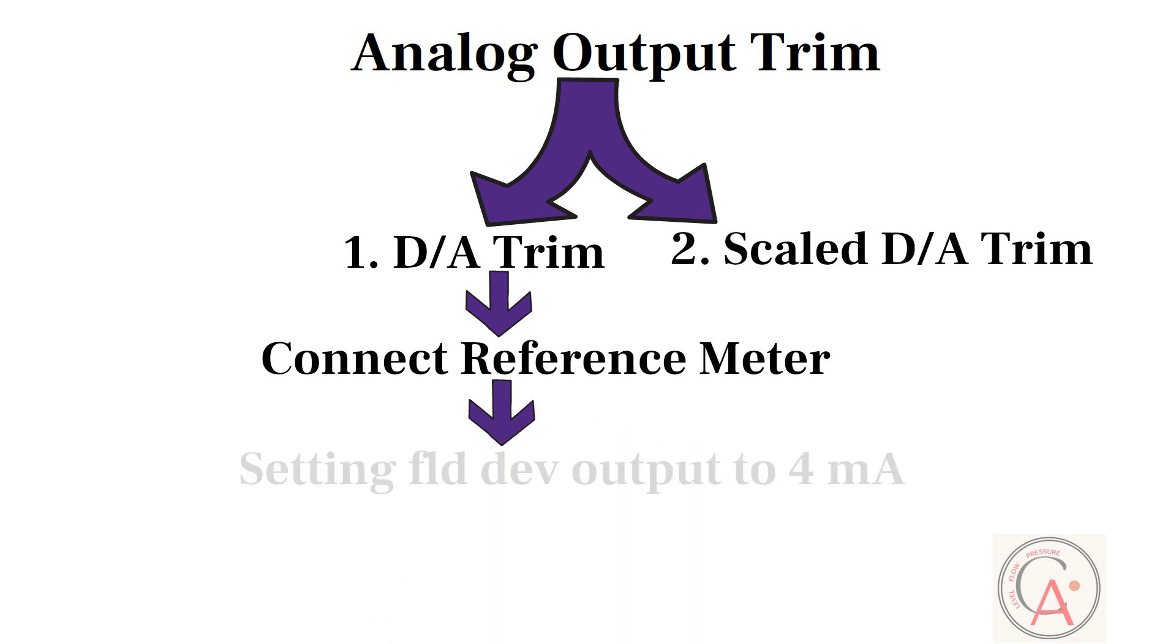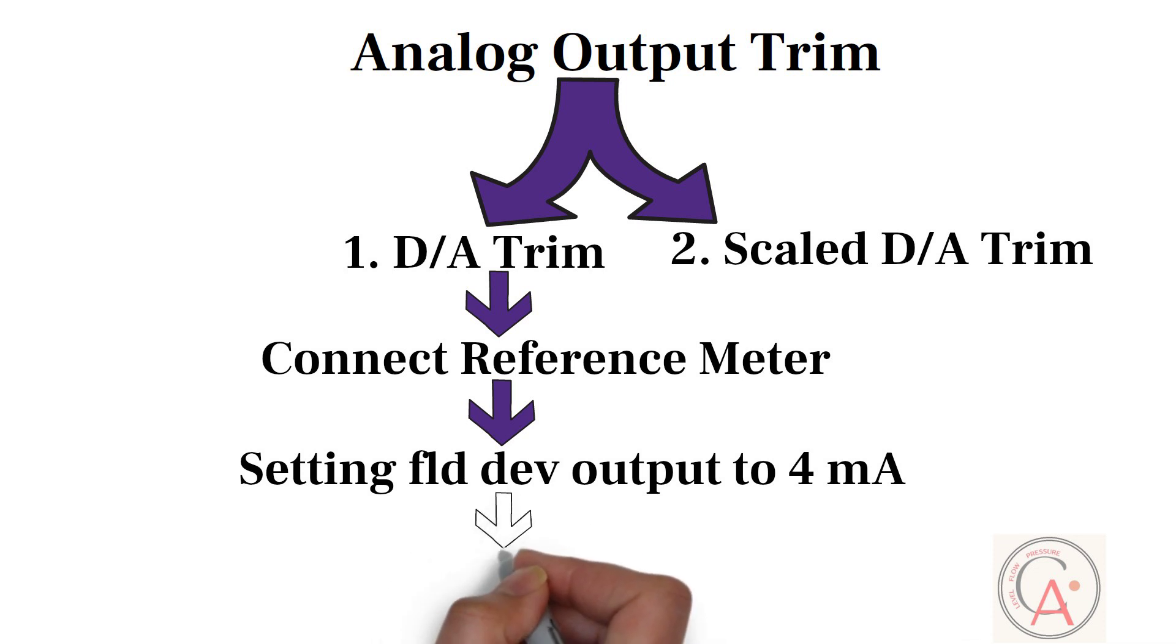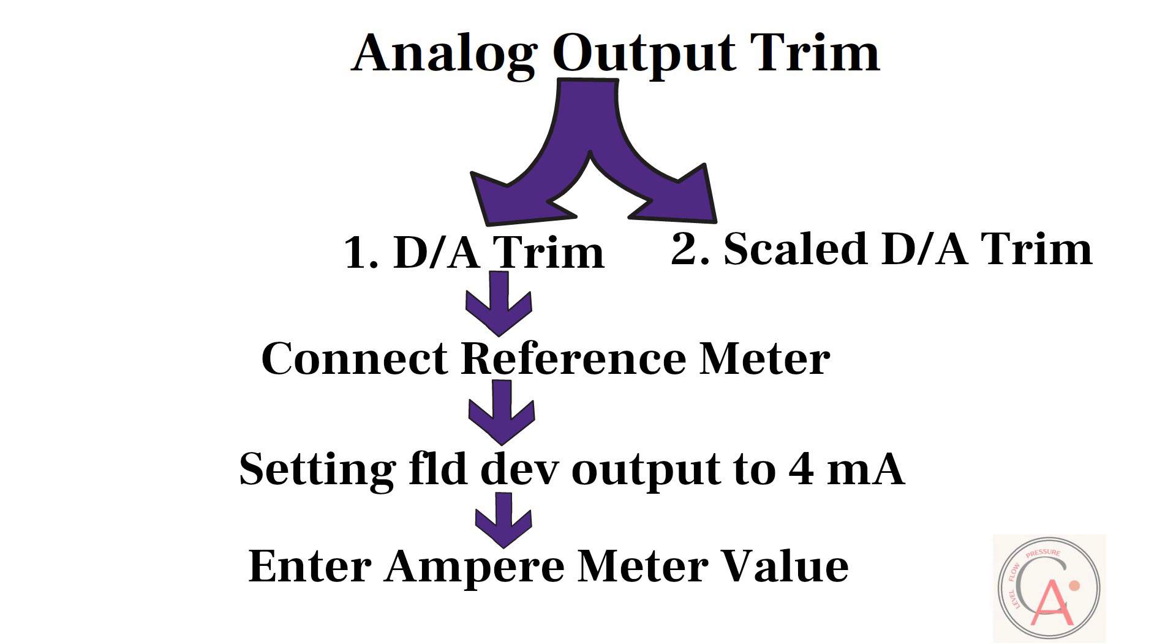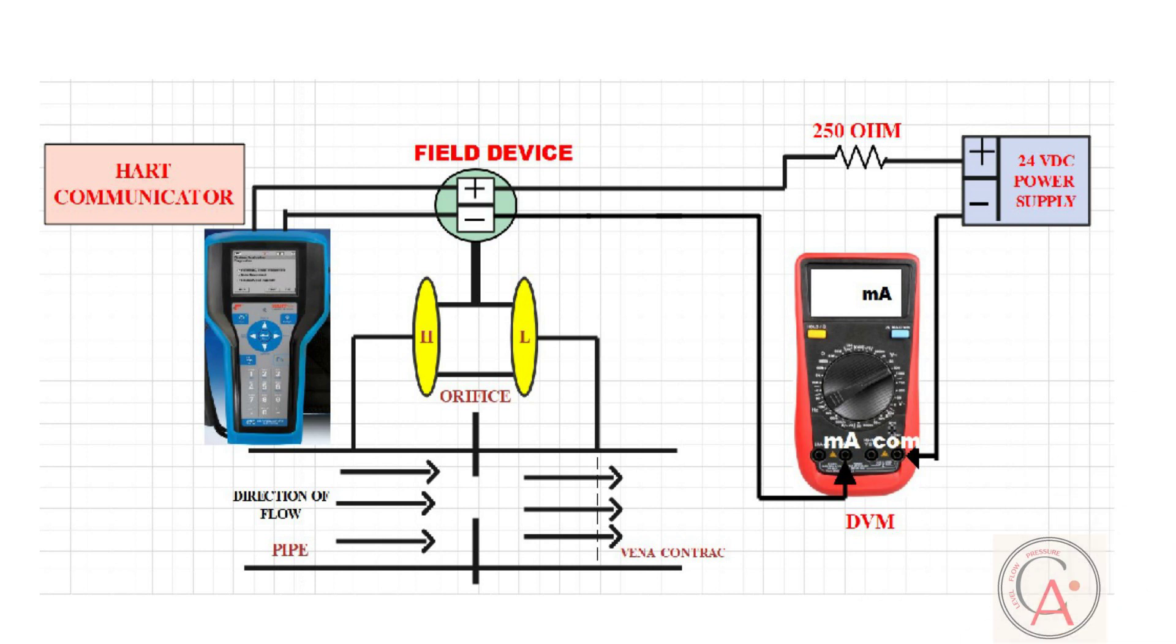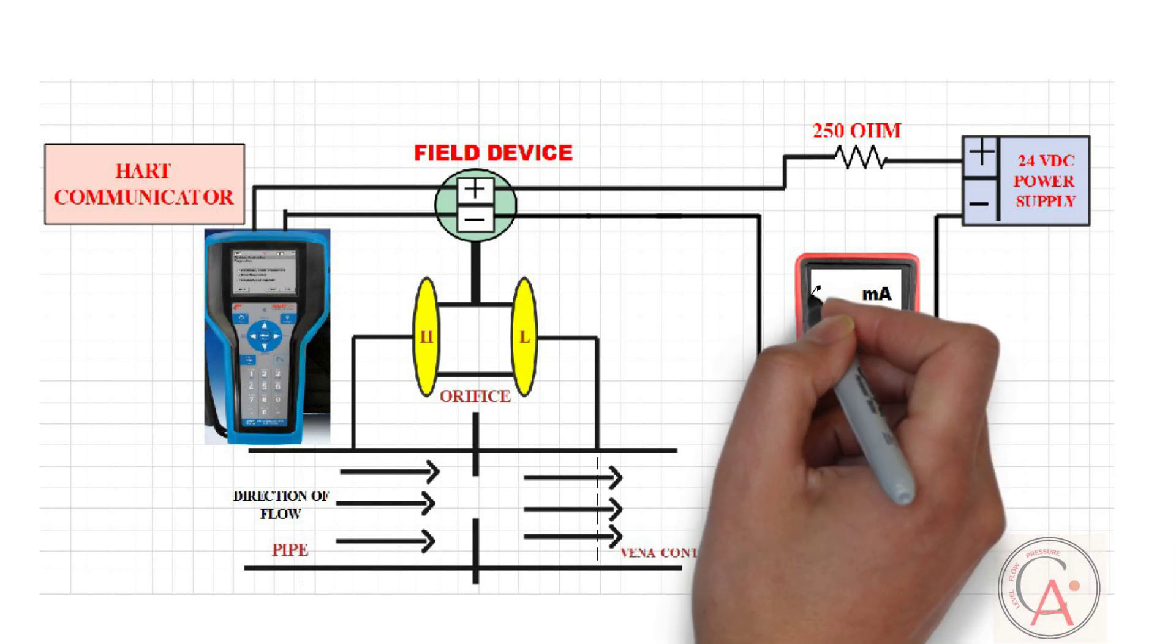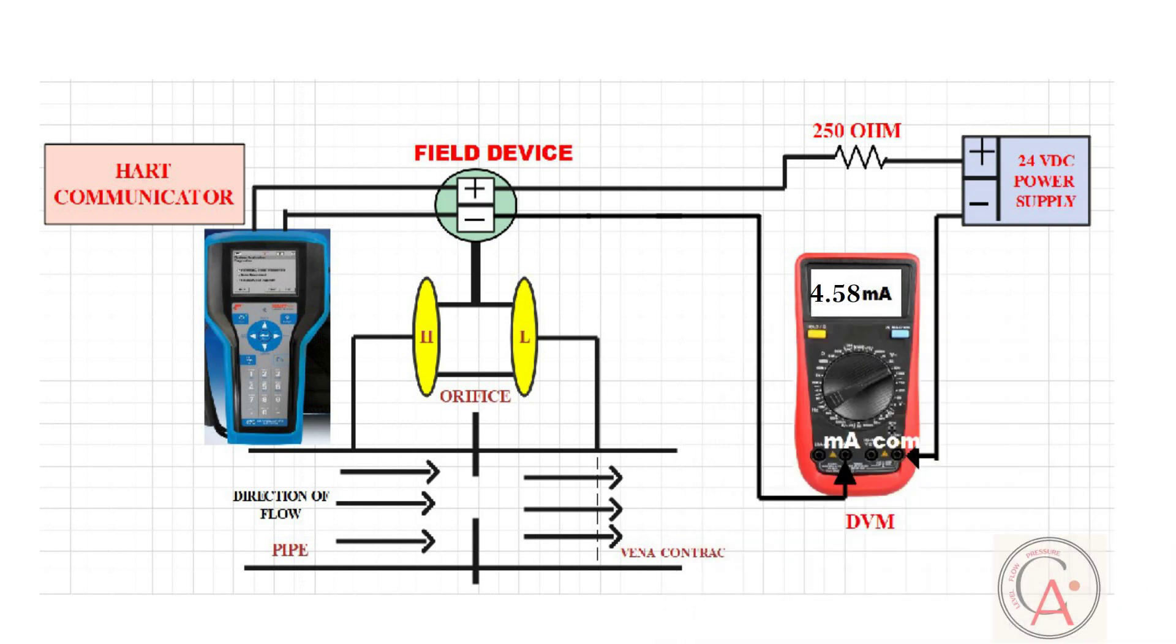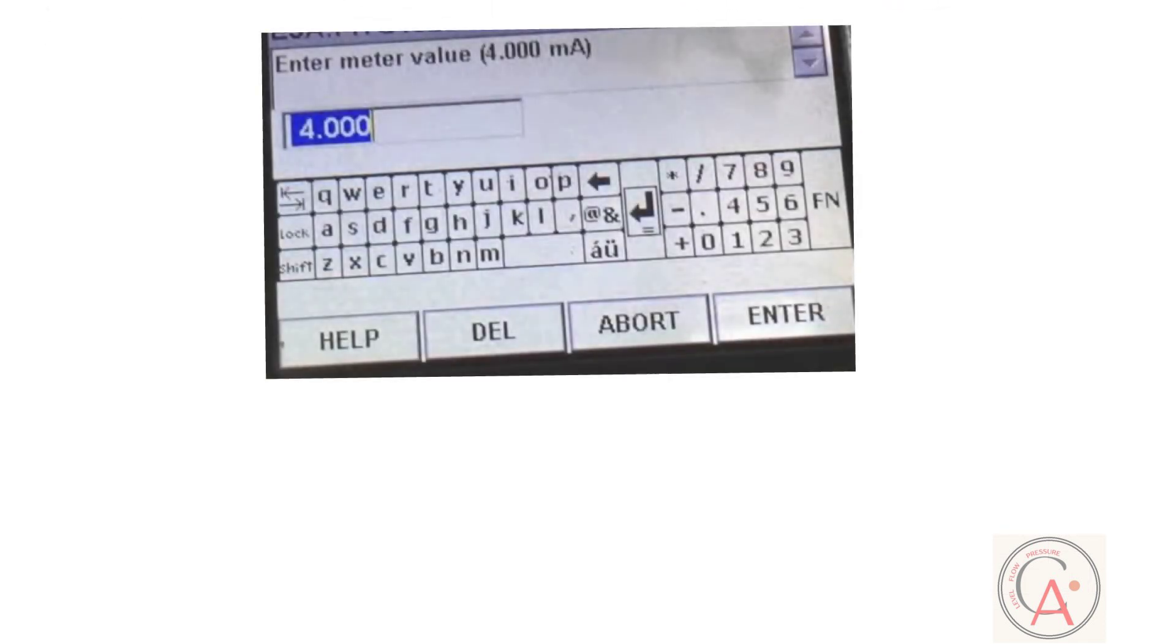Once you press ENTER button, setting field device to 4 milliampere message will appear on the screen. At this time, enter the value of ampere meter into HART communicator and press ENTER button. For example, if ampere meter value is 4.58 milliampere at 0 inches of H2O pressure, then enter 4.58 into HART communicator and press ENTER button.